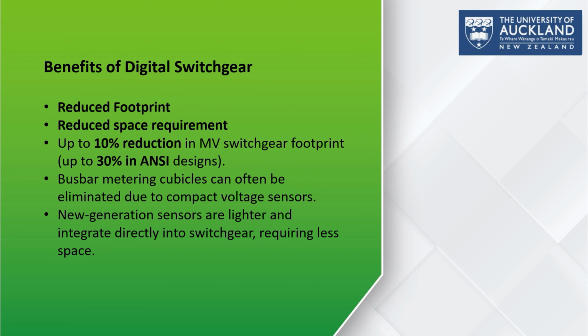Another important advantage of digital switchgear is the reduced physical footprint. Compared to conventional medium voltage switchgear, digital switchgear can reduce the footprint by 10%, right? This is possible because certain cubicles, such as the busbar metering cubicle, can often be removed. Voltage sensors and other digital components take up far less space than traditional metering equipment, right?